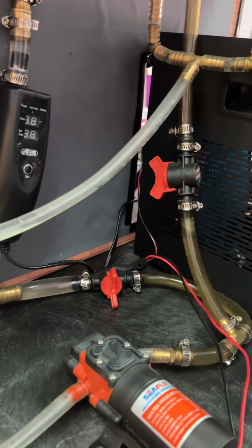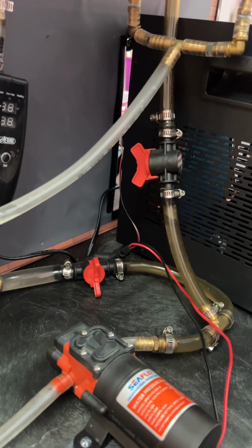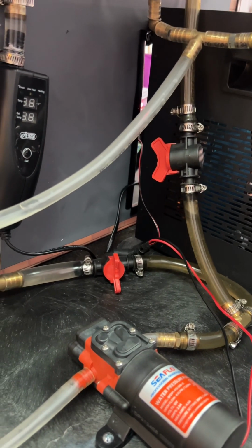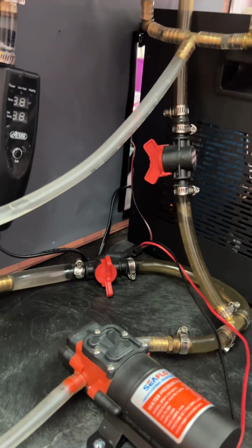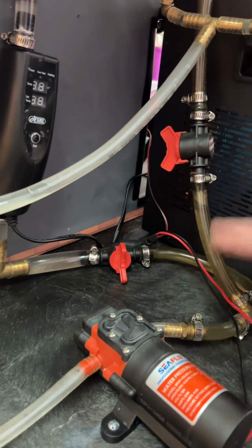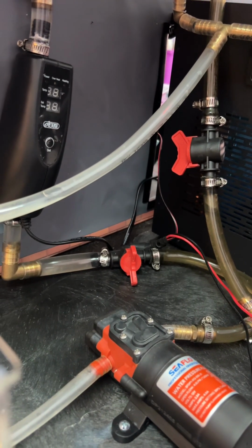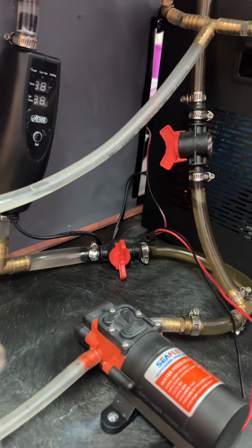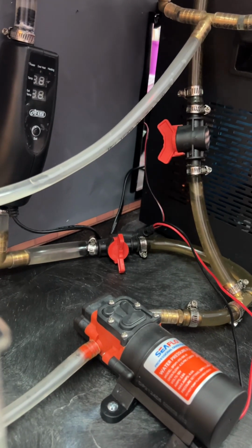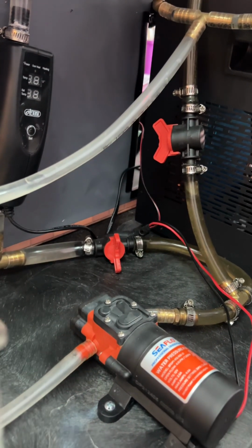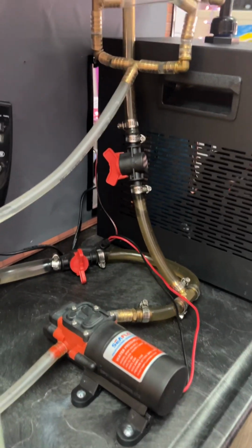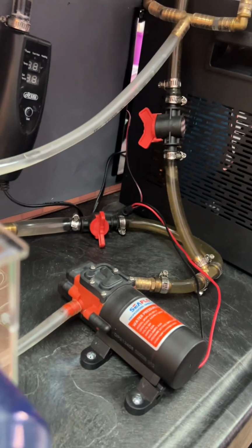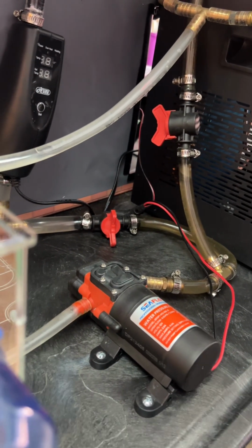In this building, in the actual school, the valves would be all operated automatically. There's a whole control system, electrically actuated valves, and the system will switch the valves to heat or cool. It can even be controlled to automatically do it depending on what temperature it is outside. If it's hot out, go to cooling. If it's cold out, switch to heating automatically. So there's smart technology in there, basically. Or it can be done by manual commands through the control system. But either way, it's all automated.